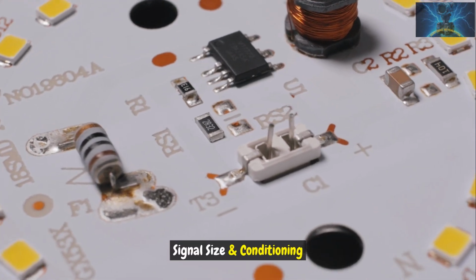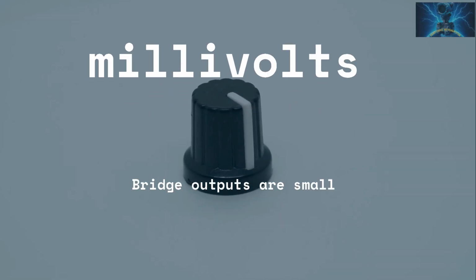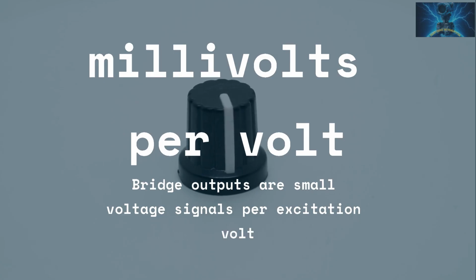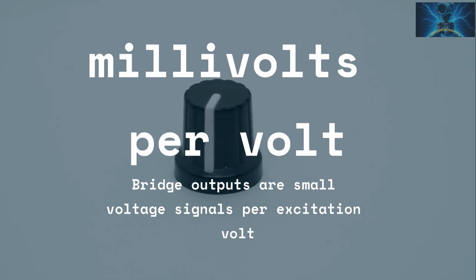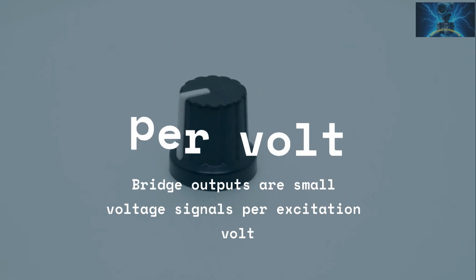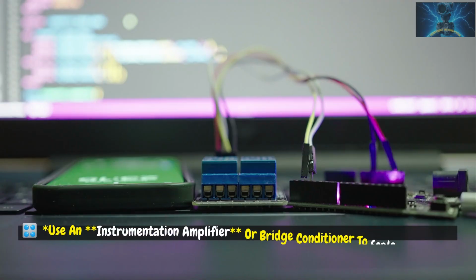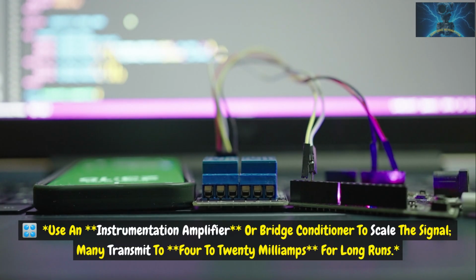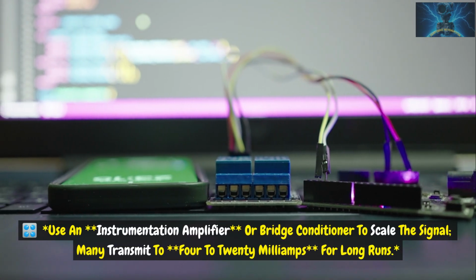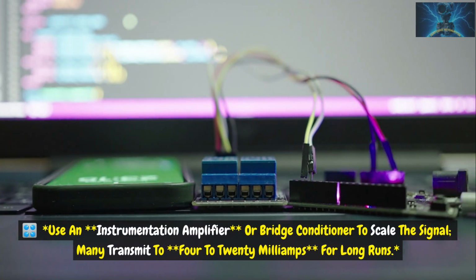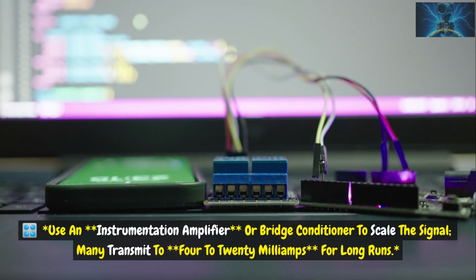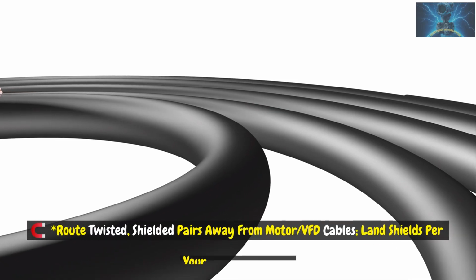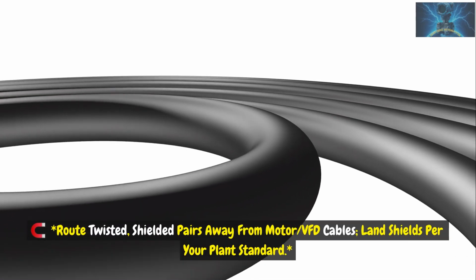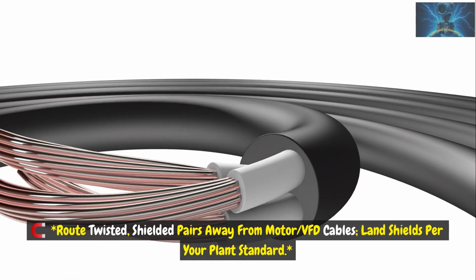Signal size and conditioning. Bridge outputs are small, often millivolts per volt of excitation. For example, 2 millivolts per volt. Use an instrumentation amplifier or bridge conditioner to scale the signal. Many transmit 4 to 20 milliamps for long runs. Route twisted shielded pairs away from motor VFD cables. Land shields per your plant standard.